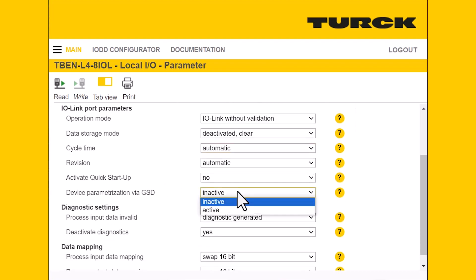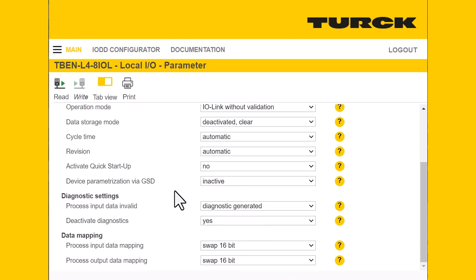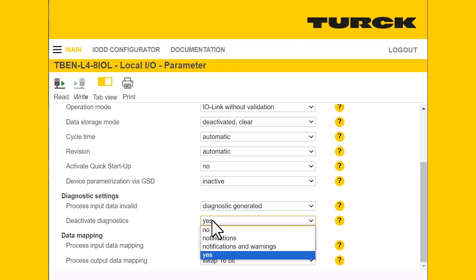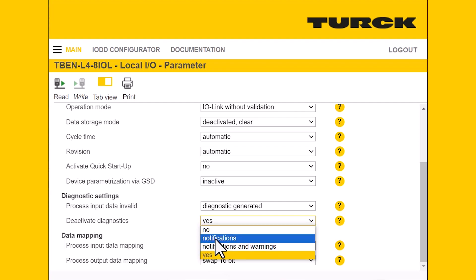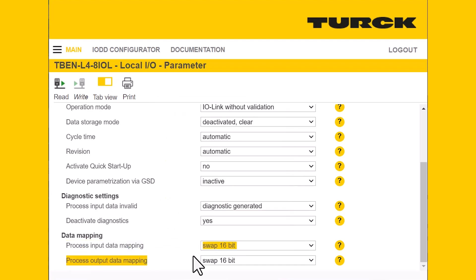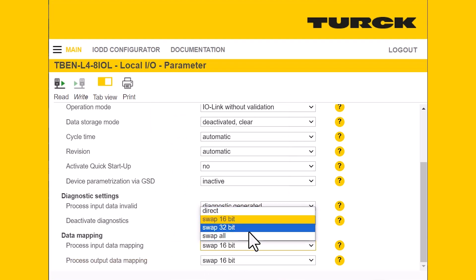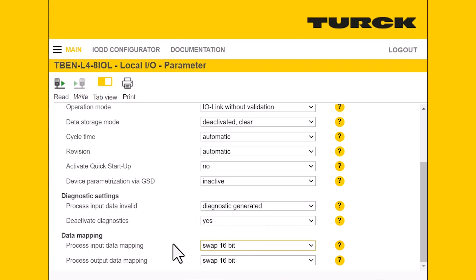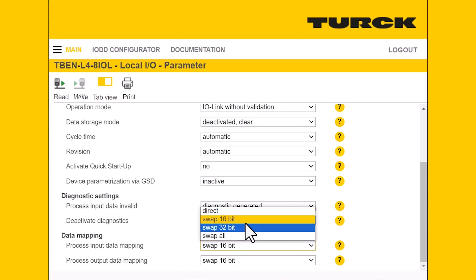You can indicate whether you're using GSD files to parameterize the device. There are also diagnostic settings — you can turn diagnostics off by clicking yes, or leave them on by clicking no. You can choose to get notifications, or notifications and warnings. You can also generate diagnostics about your process input data. Perhaps most importantly, you can alter your process input data mapping — generally it's set to swap 16 initially, and you can change it to direct, swap 32, swap all, or the default swap 16. This is very useful if you're getting process data that doesn't seem to make sense.